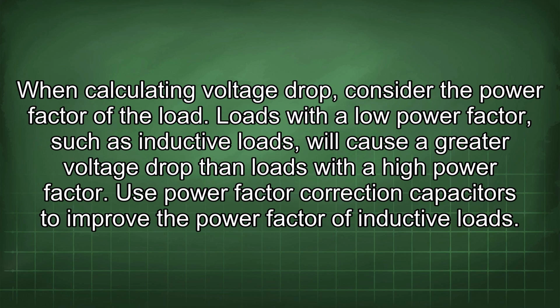When calculating voltage drop, consider the power factor of the load. Loads with a low power factor, such as inductive loads, will cause a greater voltage drop than loads with a high power factor. Use power factor correction capacitors to improve the power factor of inductive loads.